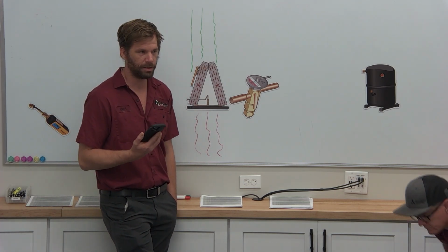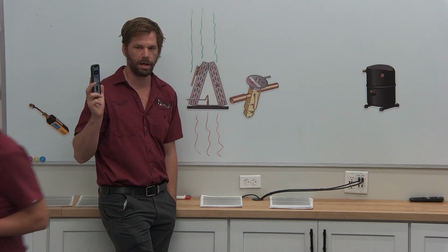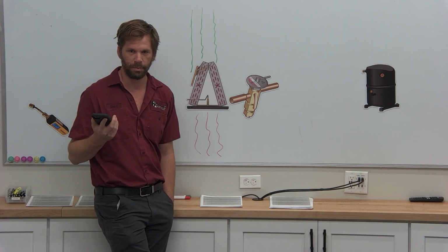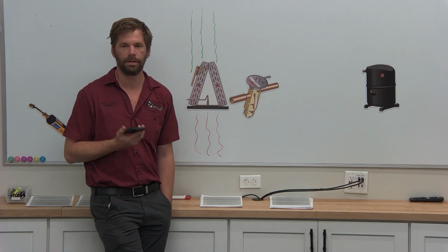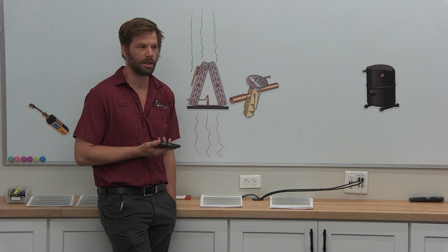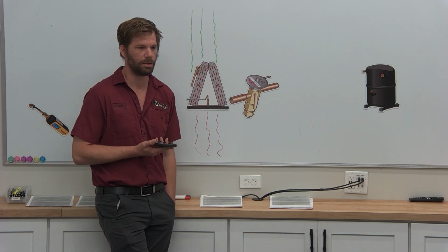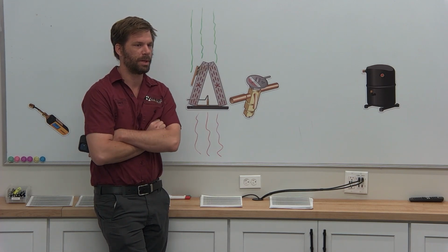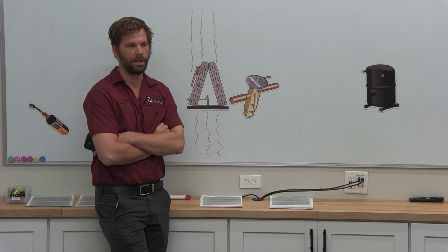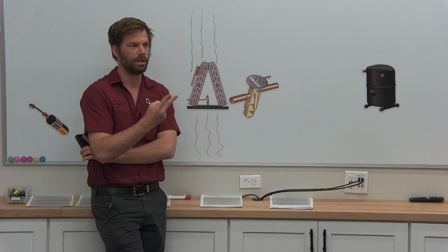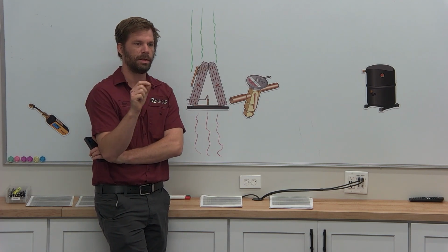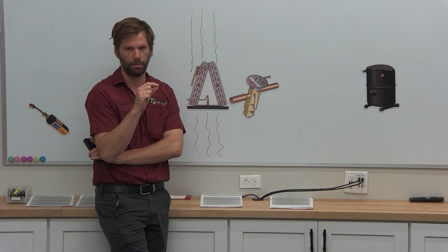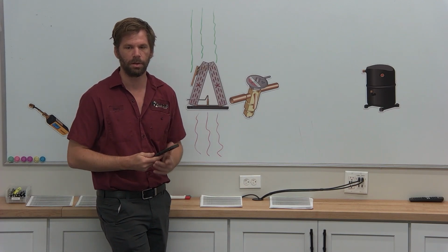So if this thing tells you a 16 degree split is the target, it's probably 17 or 18, if you have a properly set up 350 per ton AC system. Now on Carriers, it can be quite easy. Typically the tube blower tap, which is coming from the manufacturer, is your 350 per ton.